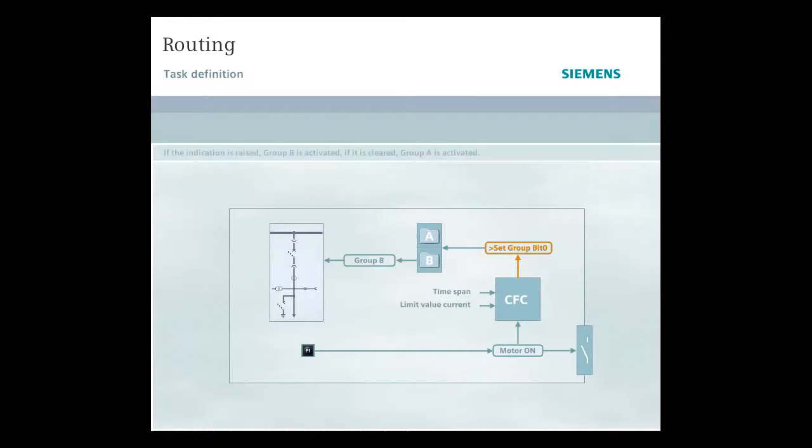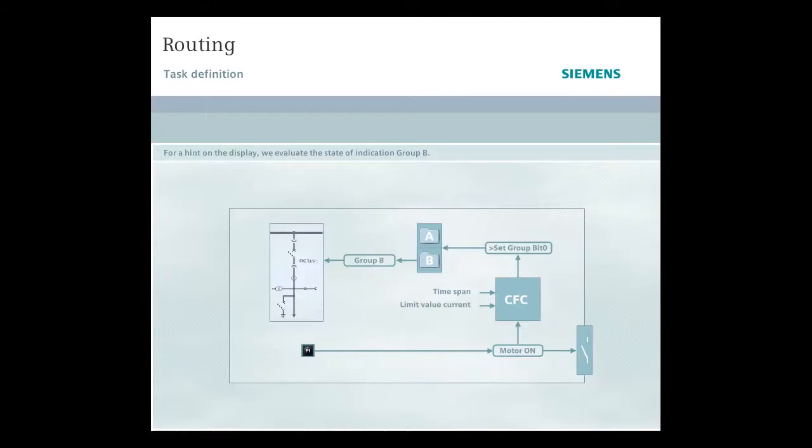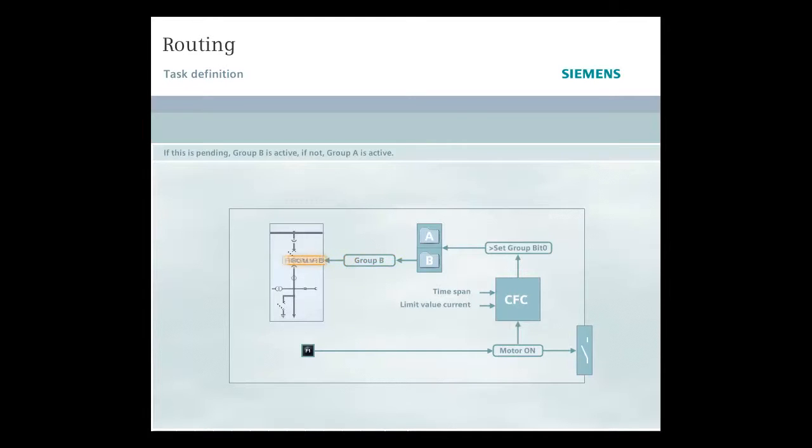If the indication is raised, Group B is activated. If the indication is cleared, the system switches over to Group A. In order to place information on the screen showing which group is currently active, we evaluate the state of indication Group B. If this is pending, Group B is active. However, if this is not pending, then in our example at least, Group A must be active.